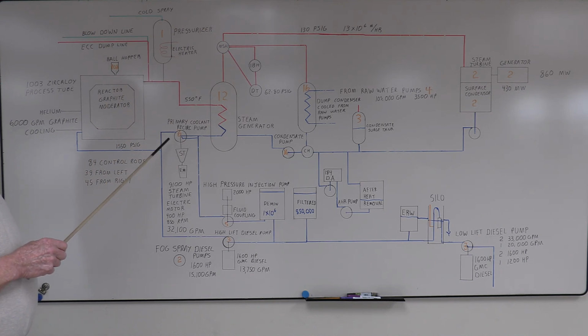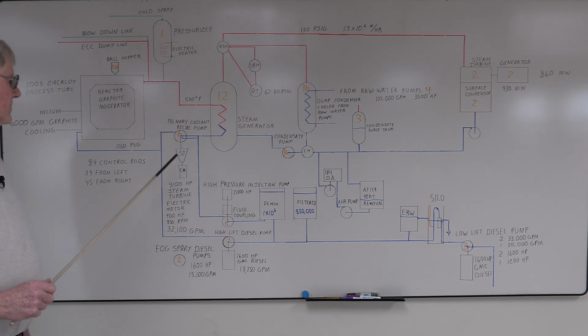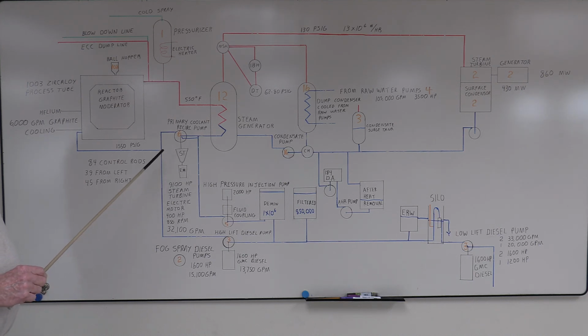The primary coolant pumps, there's 6 of them. They're steam turbines with electric motor on the shaft. They're 9,100 horsepower steam turbines, condensing. The condenser used steam jet air ejectors to pull a vacuum on it. There's also a hogger for starting up. Some plants use vacuum pumps. This plant used steam jet air ejectors.